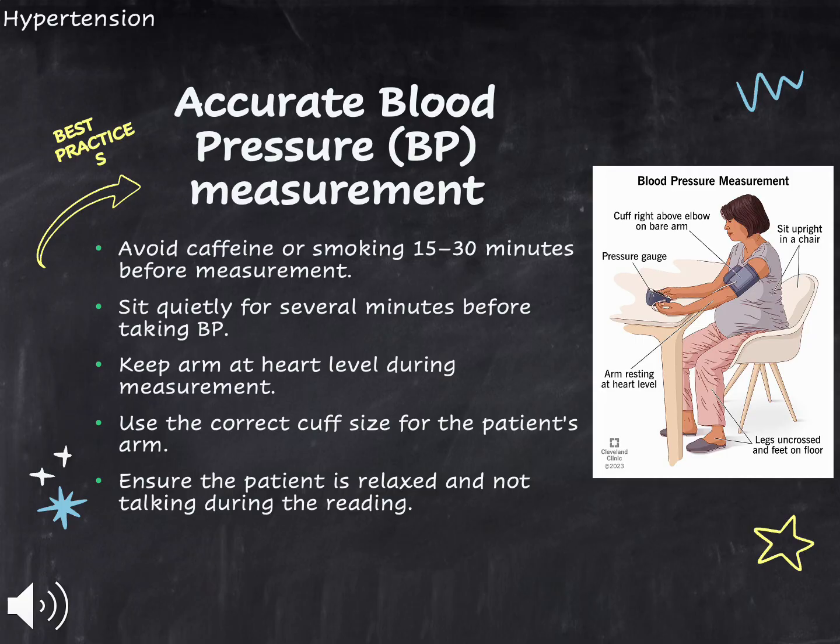Use the correct cuff size. Too small will give a false high, and too large a false low. Also, avoid measuring immediately after exercise or emotional stress, as both can skew results.